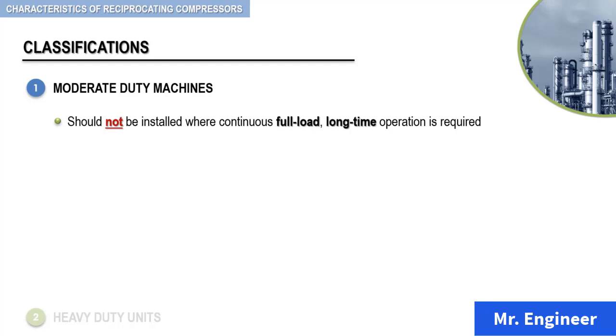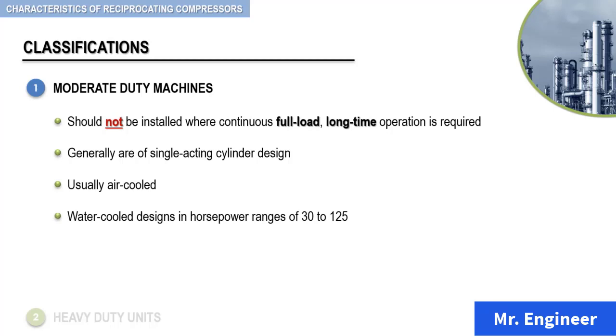In general, moderate-duty compressors are of single-acting cylinder design. Usually, these compressors are air-cooled. However, they are also offered as water-cooled designs in horsepower ranges of 30 to 125. They are built as single-stage units for pressure ratings up to 50 psi and as two-stage units up to 250 psi.